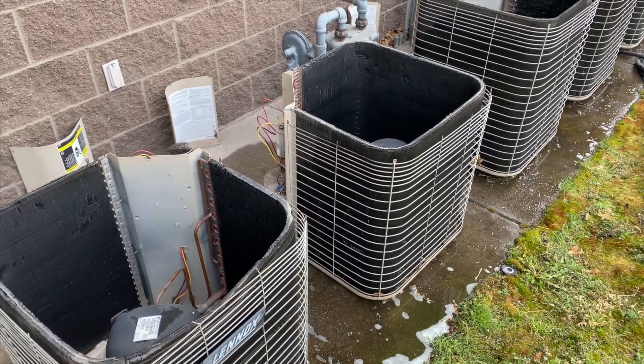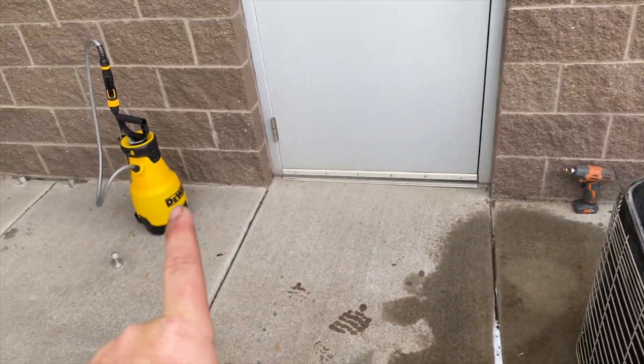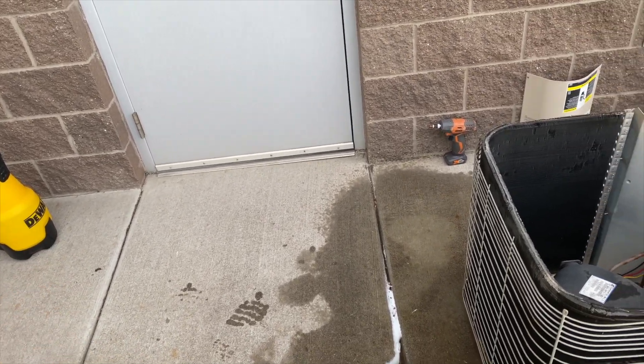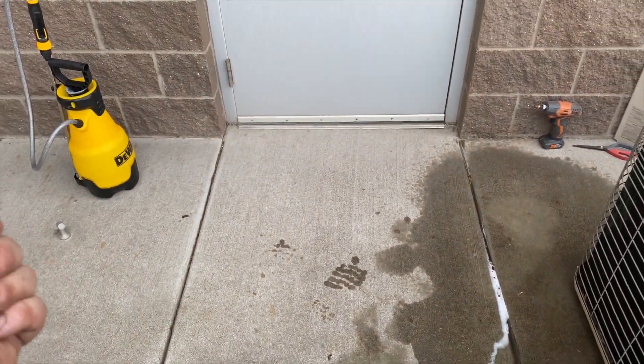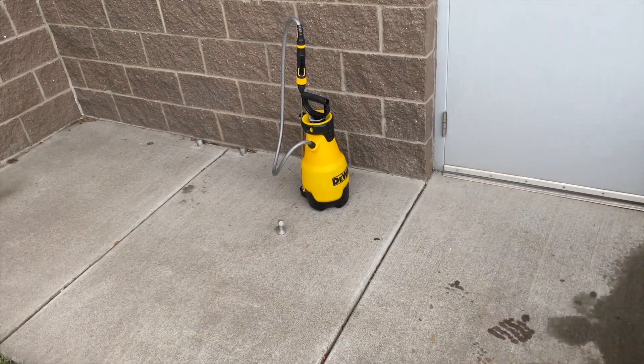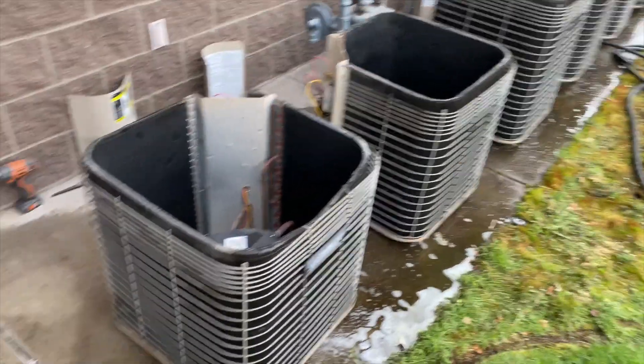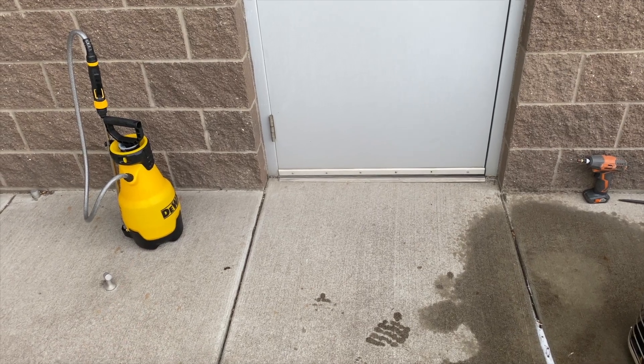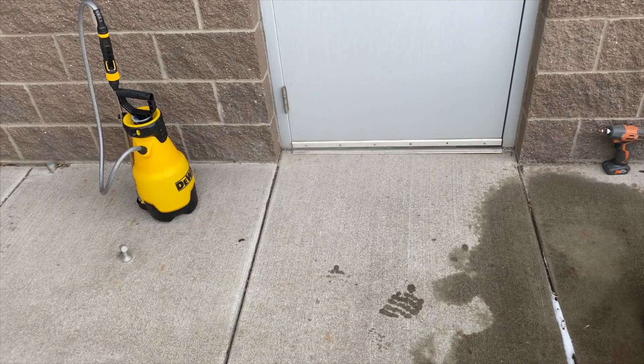We got them all treated with coil cleaner and I'm letting it sit. While it was sitting, I went ahead and hosed out the pump sprayer — got all the coil cleaner out of it and filled it with water, then bled it until no more soap came out. It's very important to do that, otherwise the coil cleaner will eat up the sprayer. This DeWalt one was about $30, versus the usual $10 I spend, so we'll see if it lasts longer.